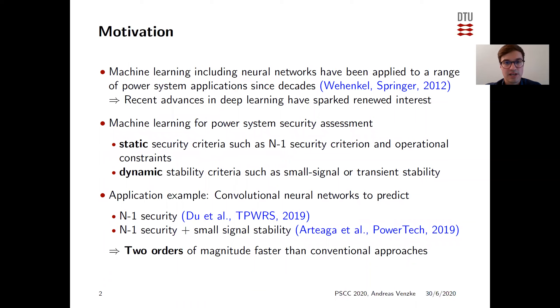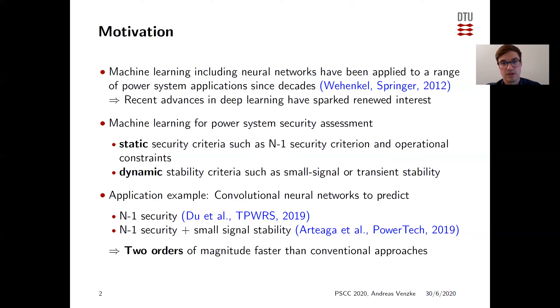One promising application is to use machine learning for power system security assessment — that is to screen a large number of operating points for static security criteria such as N-1 security criterion and operational constraints, and dynamic stability criteria such as small signal or transient stability. One example from literature uses convolutional neural networks to predict N-1 security and small signal stability, showing that these are about two orders of magnitude faster than conventional approaches.